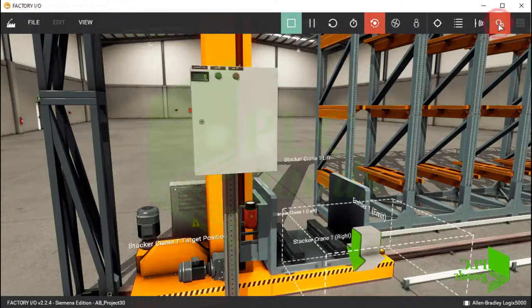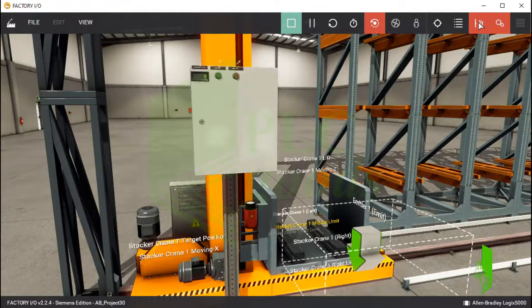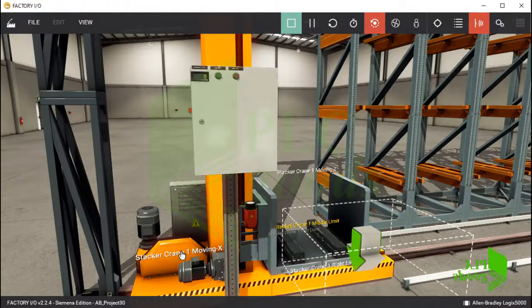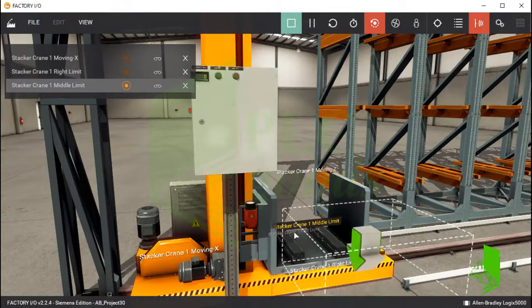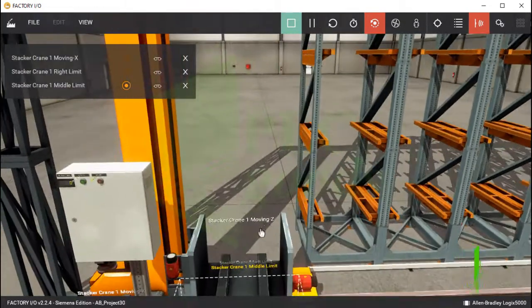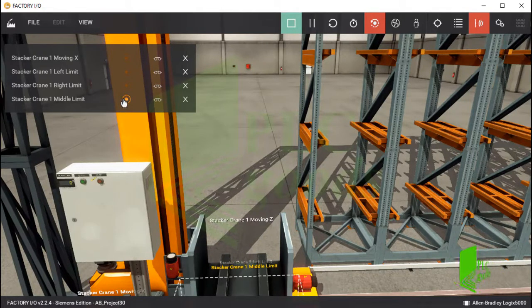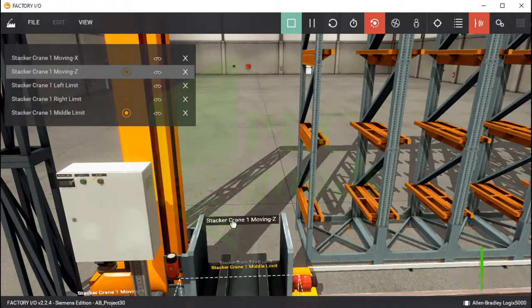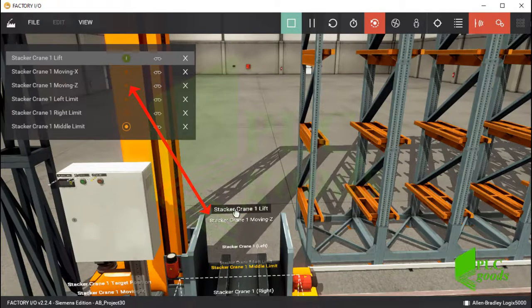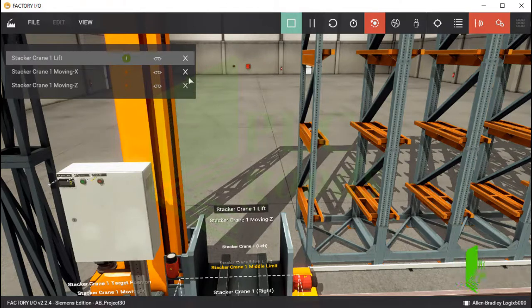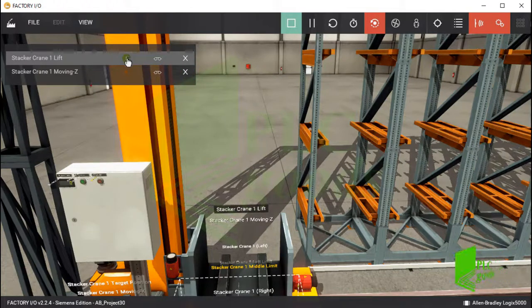We have used these actuators in lesson number 28. Each actuator has a sensor that can send the actuator state to my controller. This boolean tag will be one when the crane is changing its position. The controller can use these three tags to detect the crane arm positions — right side, middle, or left side. Now the middle sensor is activated. Also this tag will be one if the crane is moving in the vertical direction. My controller will use these sensors to detect the appropriate time to exit from a step in the sequential program.